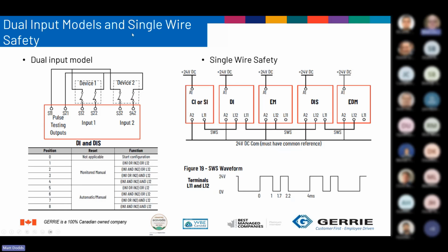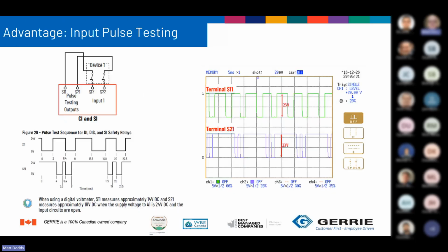Single wire safety. If you're trying to upgrade an older MSR 300 system or try to achieve a higher level of safety with electromechanical relays, the connections are numerous. With the 440R, you can simply run a single wire, and you can see the pulse waveform there that it puts out to the next relay as kind of a keep alive signal. So great option, and again, reduce a lot of wiring, gives you a lot of flexibility in what you can do.